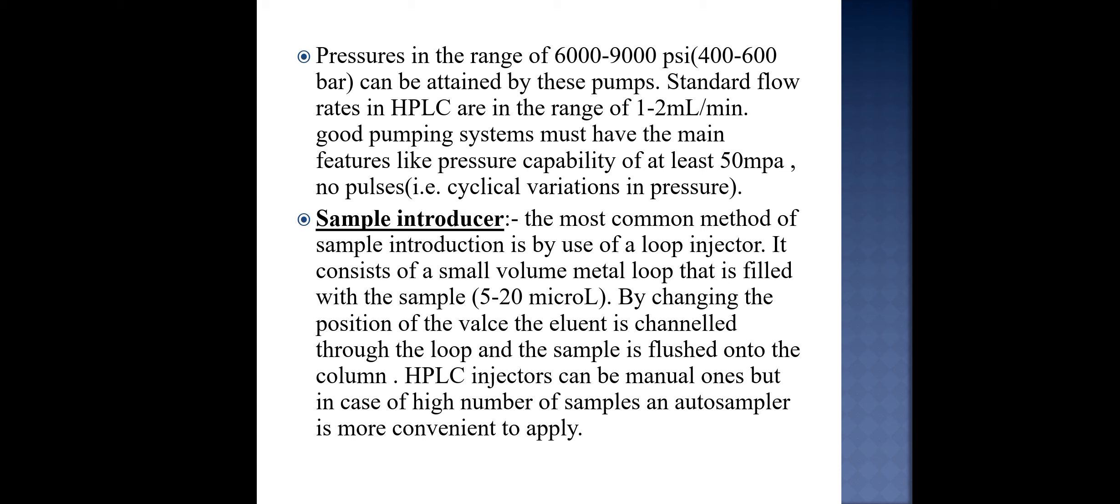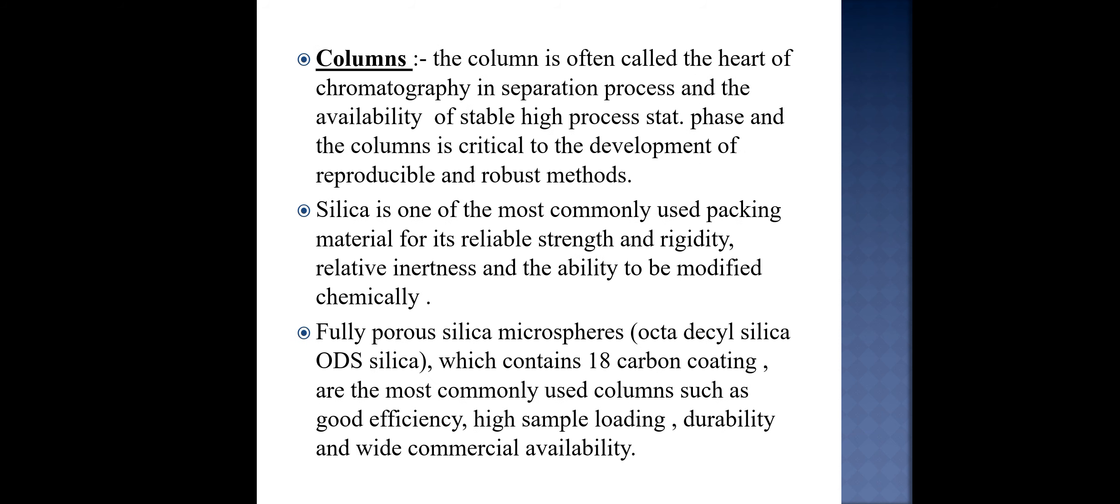The most common method of sample introduction is by the use of loop injector. It consists of a small volume metal loop that is filled with the sample 5 to 20 microliters. By changing the position of the valve, the eluent is channeled through the loop and the sample is flushed onto the column. HPLC injectors can be manual ones but in case of high number of samples an autosampler is most convenient to use.